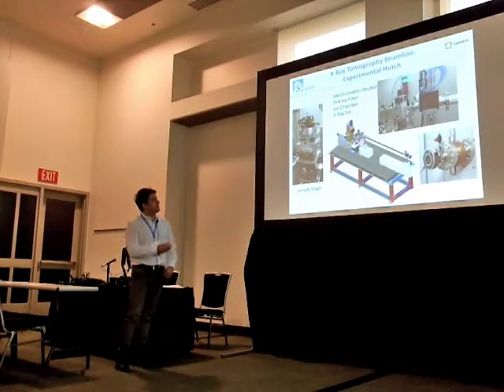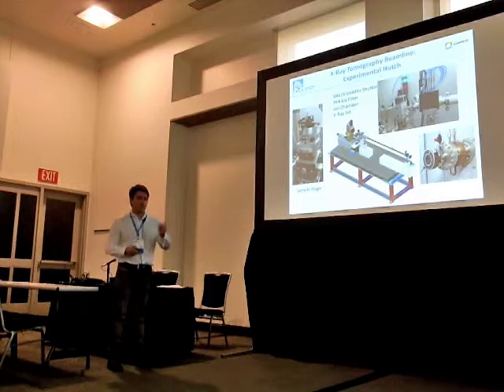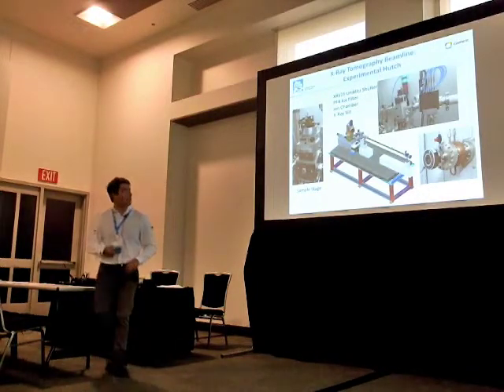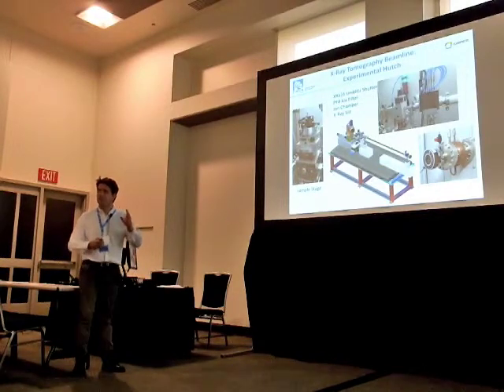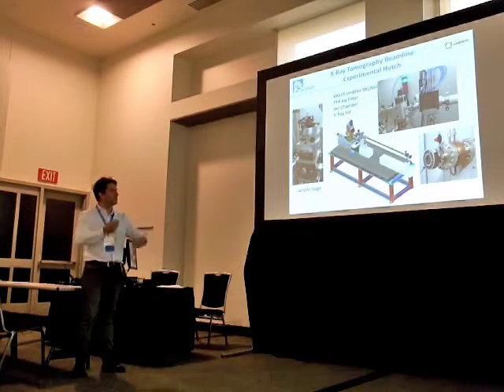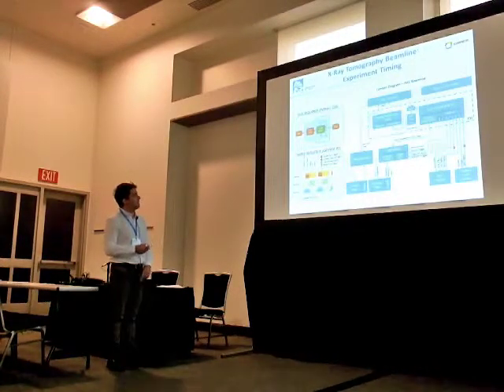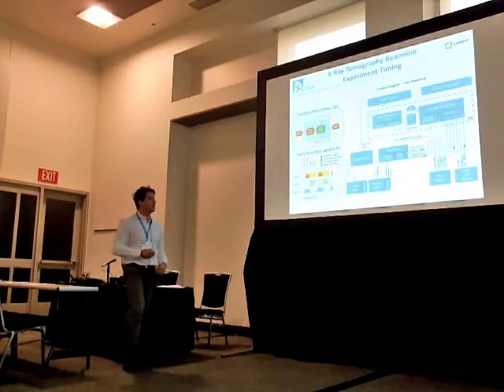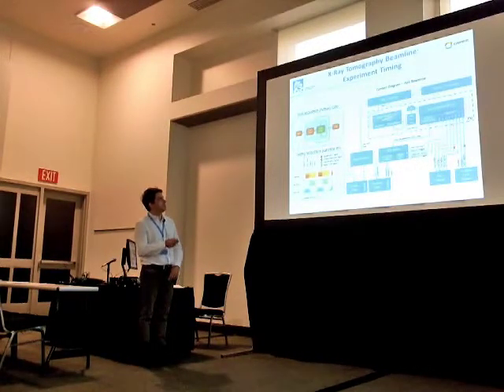Basically, this is the beamline that is controlled with the PXI to do this acquisition. We have all the sample stage. This tower is to move the sample and rotate and so on within some micron resolution. And it has to be synchronized with the detector so that you do data acquisition and rotation of your sample and opening shutters and so on. It has to be all orchestrated by a centralized system. And so we use this centralized system through the PXI. It basically handles different drivers that we have to use from different manufacturers, CCD cameras and all this stuff.